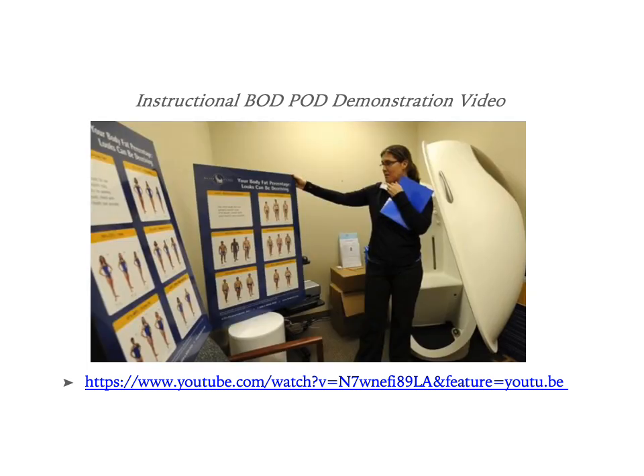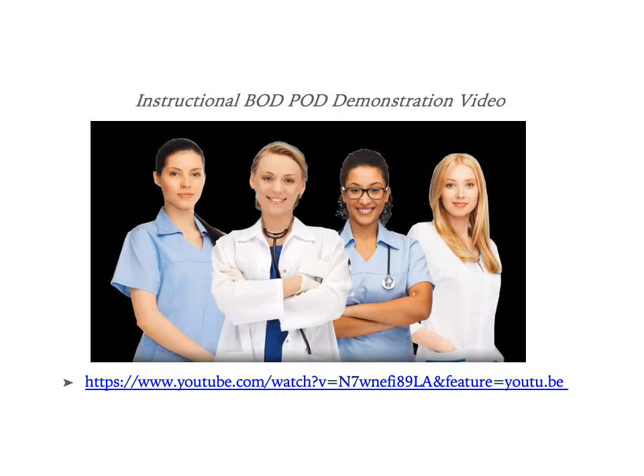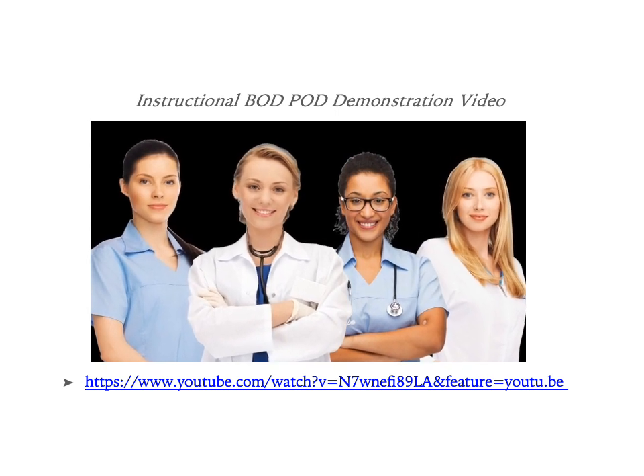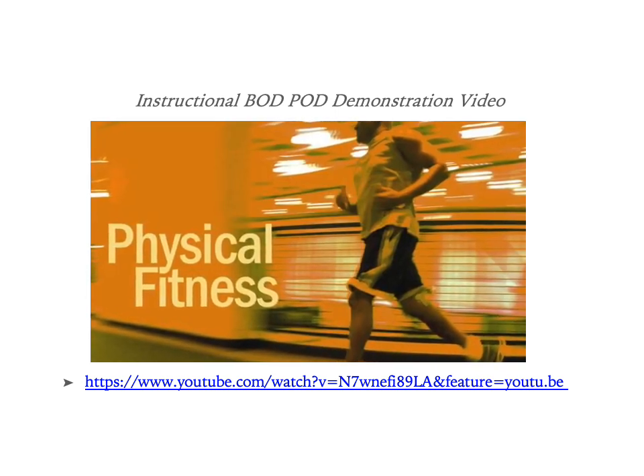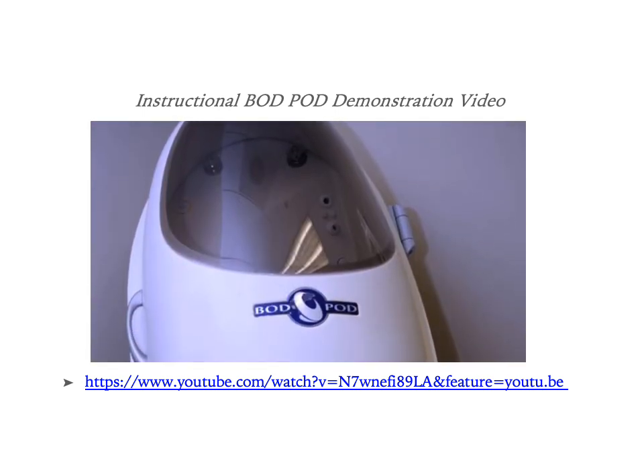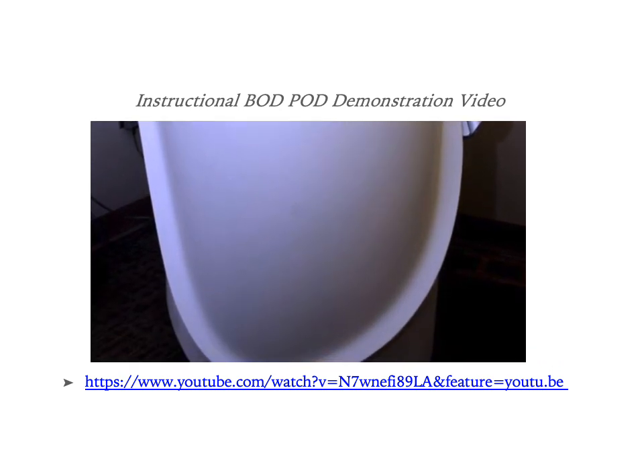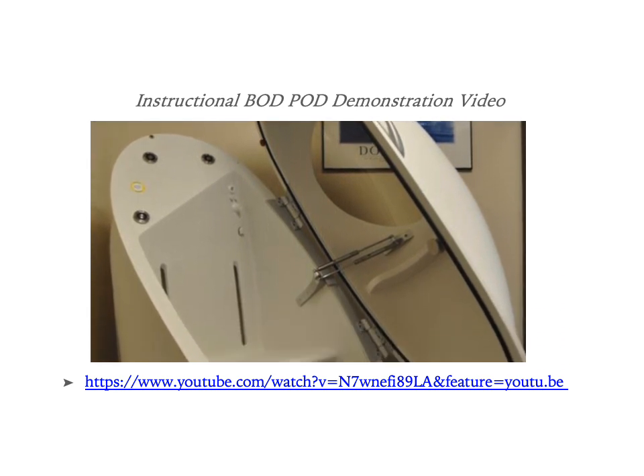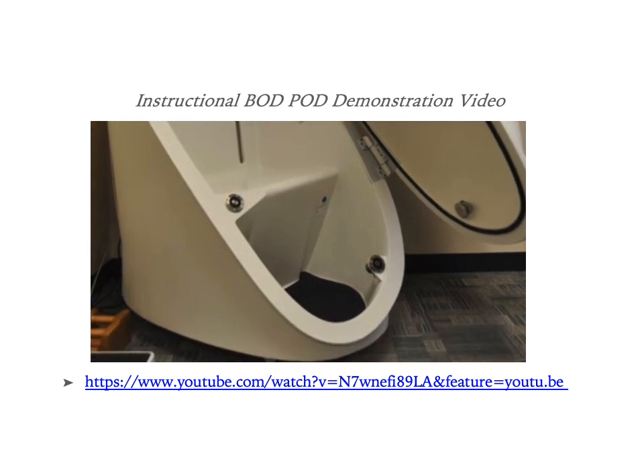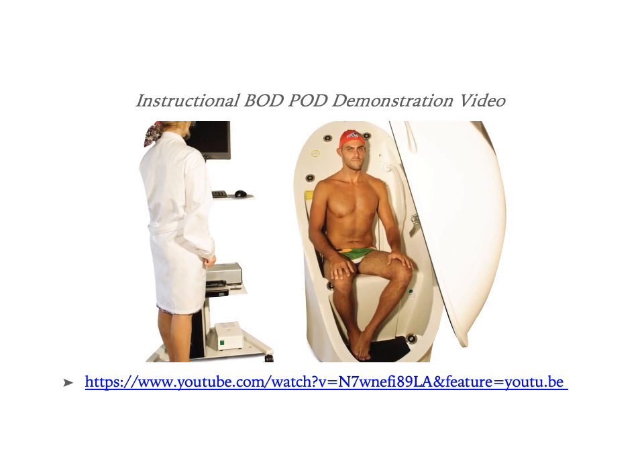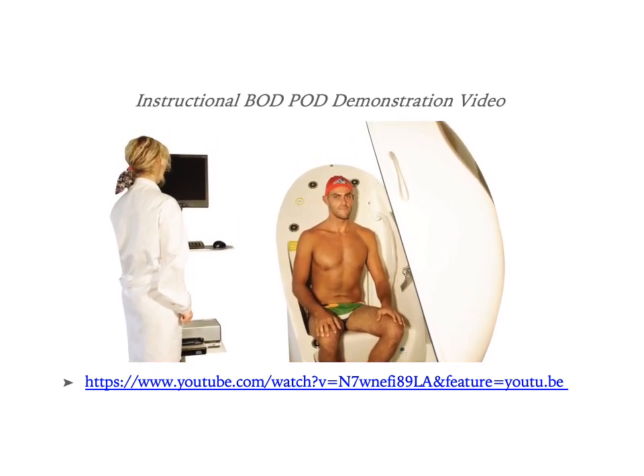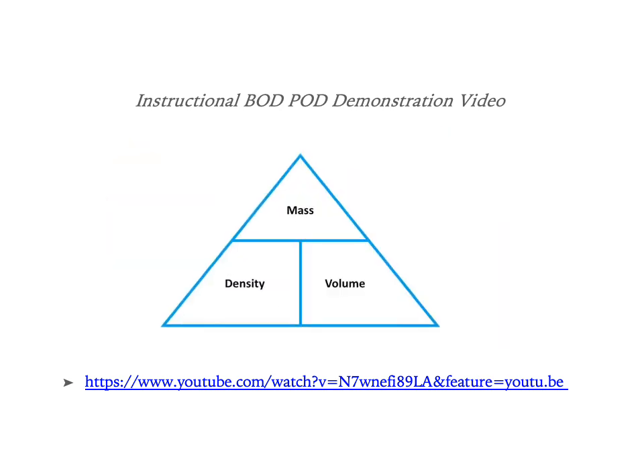Air displacement plethysmography is a technique used to determine human body composition, developed into a viable system in the mid-1990s. Plethysmography refers to the measurement of size — in this case, volume. It is a tool used by doctors, nurses, nutritionists, and athletic trainers to help patients assess their overall health and efficacy of their exercise programs. The only commercially available product using this technique is the BODPOD, made by CosMed. This device has two chambers: one for the patient to sit in and another in the back for reference pressures. Physiologically, this technology measures percent lean versus fat by measuring human body volume.